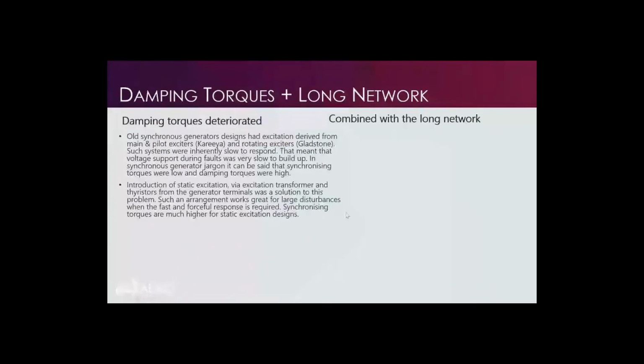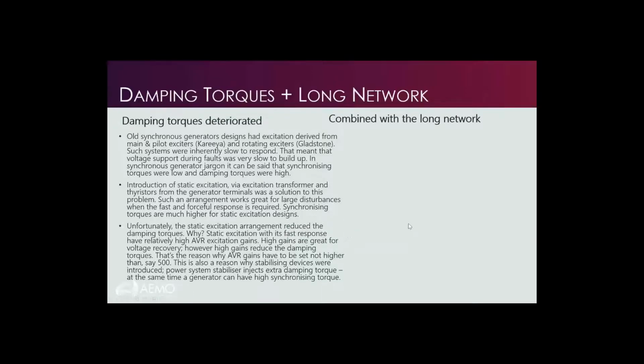So what happened some decades ago was the introduction of static excitation. That means excitation is derived from generator terminals via an excitation transformer and thyristors. Such an arrangement is great for large disturbances, because when there is a fault, such a generator would respond in a fast and forceful way. So synchronizing torques are much higher for a static excitation system than for rotating excited systems. Now, such an arrangement reduced damping torques. Why is that? Because static excitation, with its fast response, has relatively high AVR gains. And high gains are really great for voltage recovery. But these high gains reduce the damping torques.